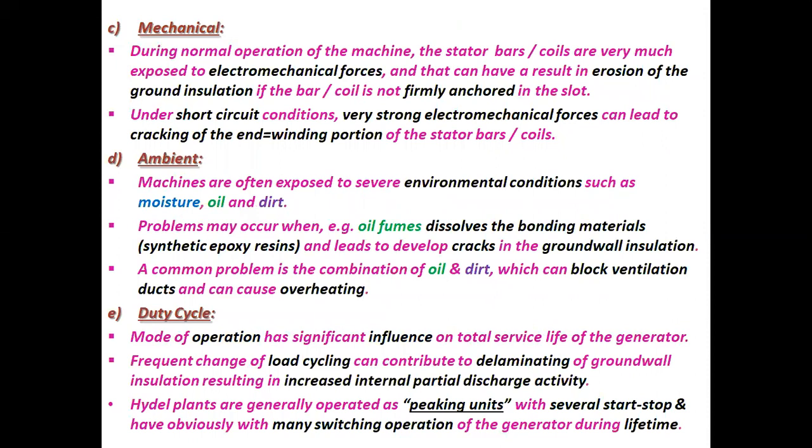C. Mechanical. During normal operation of the machine, the stator bars or coils are very much exposed to electromechanical forces, and that can result in erosion of the ground insulation if the bar or coil is not firmly anchored in the slot. Under short circuit conditions, very strong electromechanical forces can lead to cracking of the end winding portion of the stator bars or coils.